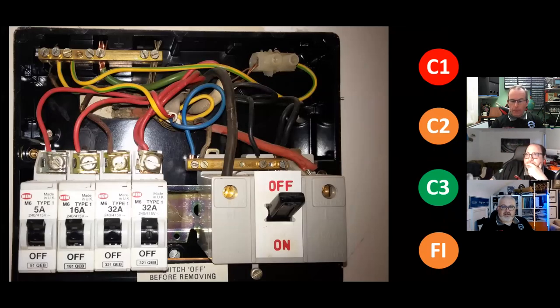Right, this one. Several things here. The main thing is look at the 32-amp circuit breaker and what's attached to it. And also look at the tails coming in, or what's left of them at least. This is not healthy. So that 32-amp one, the third one from the left. What load was on that? I can't remember, actually. I think it was a socket in a kitchen.